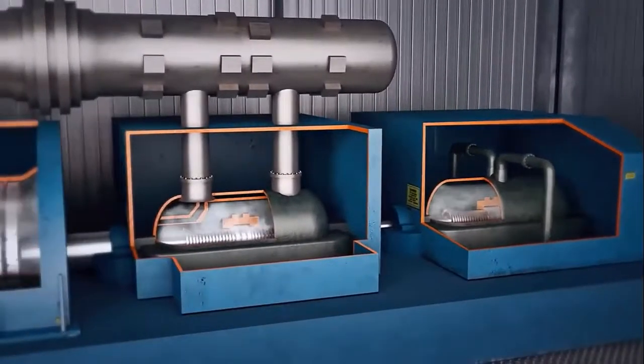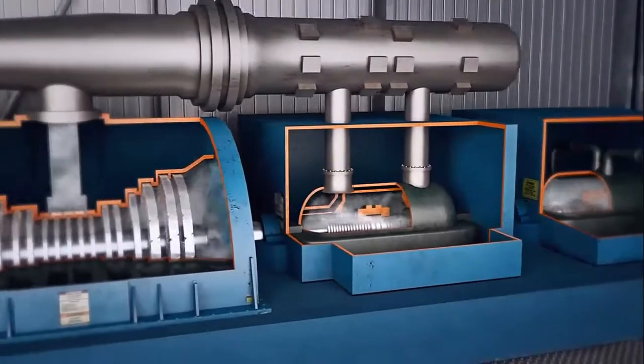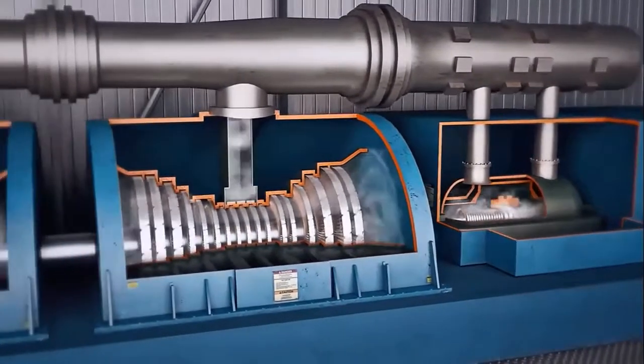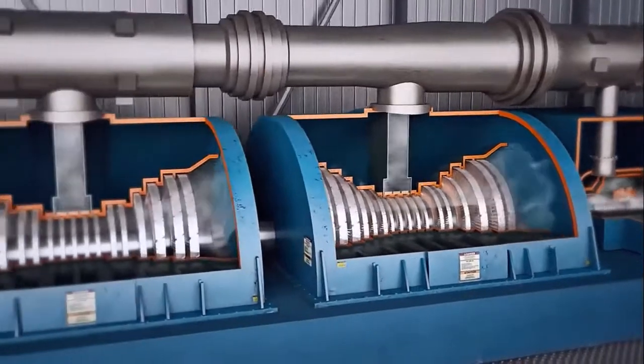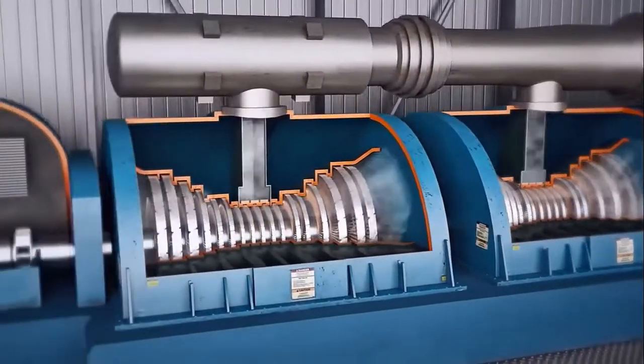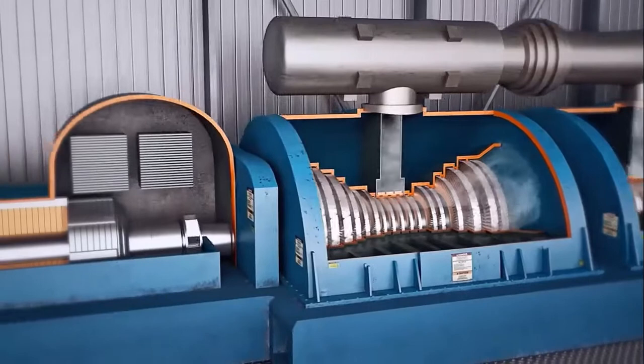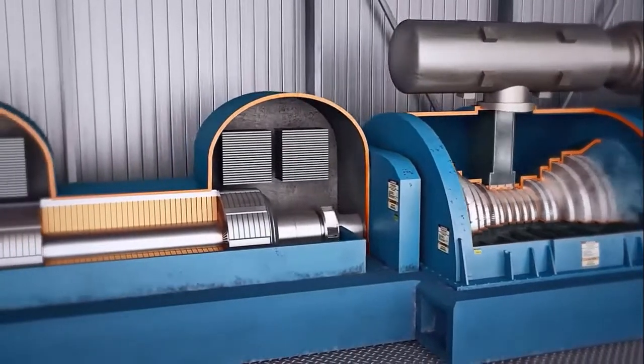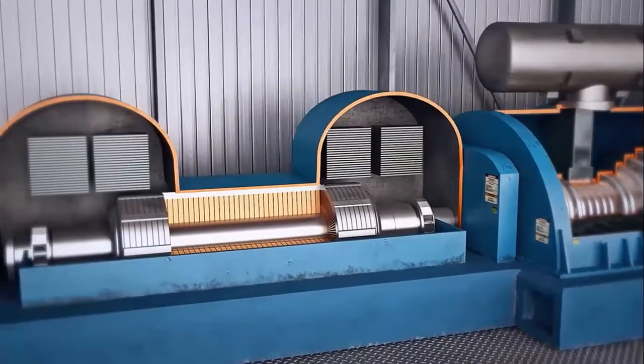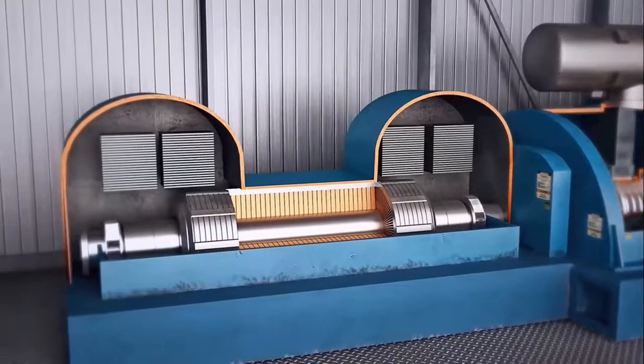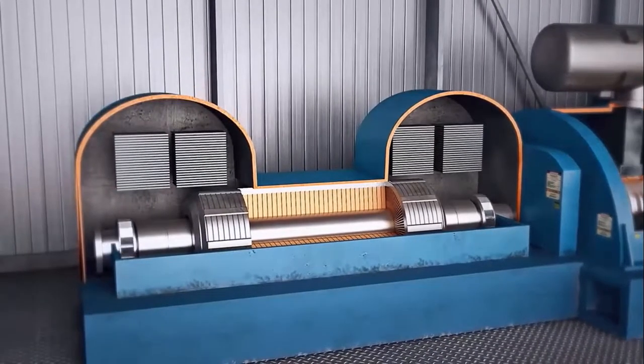The force of the steam turns the turbine shaft, which turns the generator rotor at 3600 revolutions per minute. This rotation, along with the induced current on the rotor inside the generator, produces voltage, completing the process of generating electricity. The generator output is 24,000 volts, which is stepped up to as much as 500,000 volts for transmission.